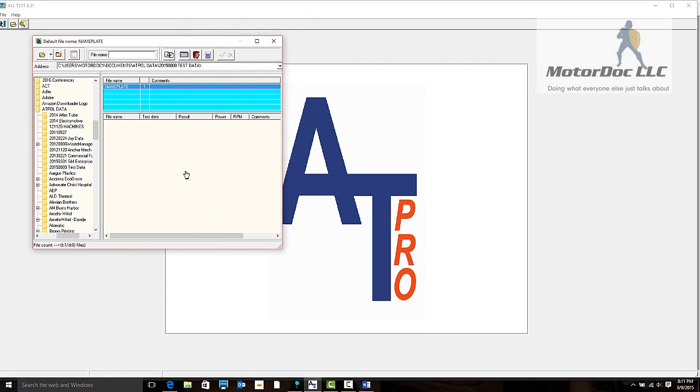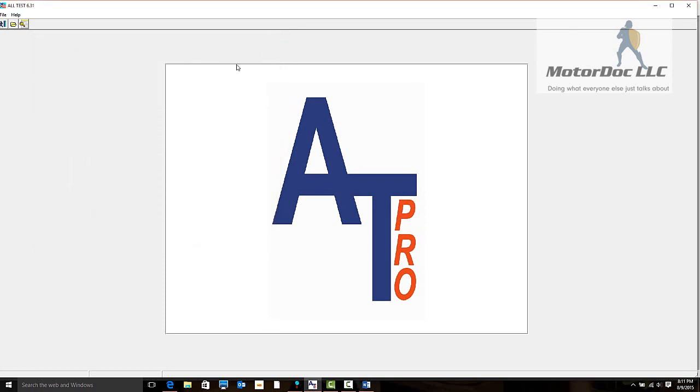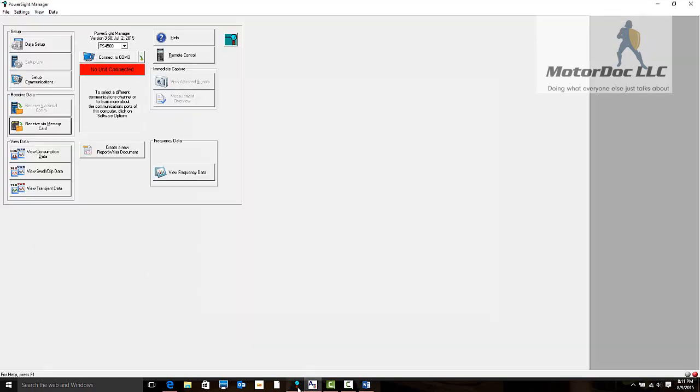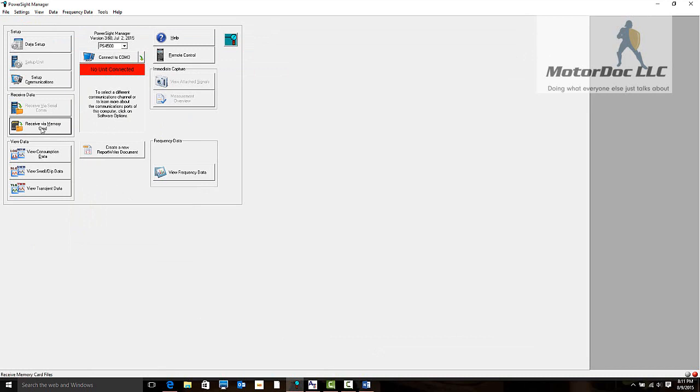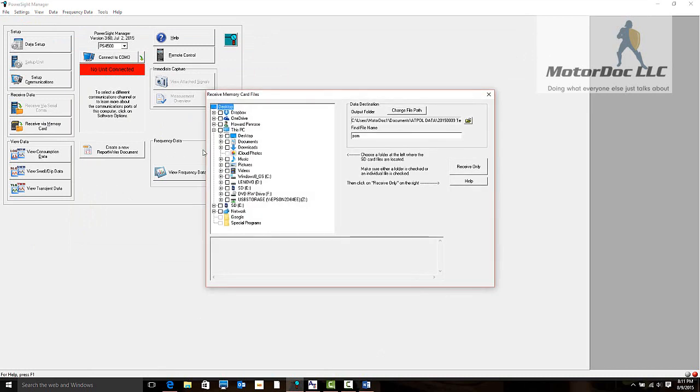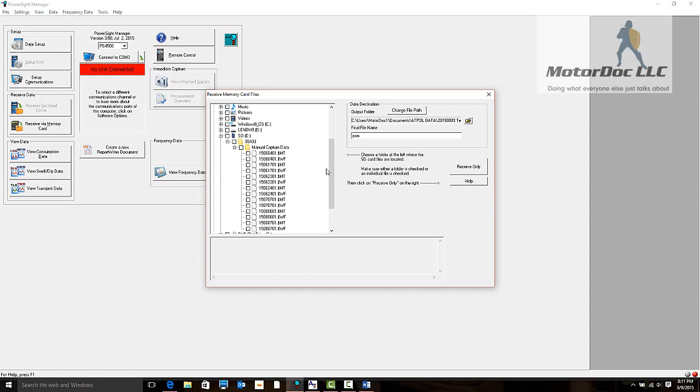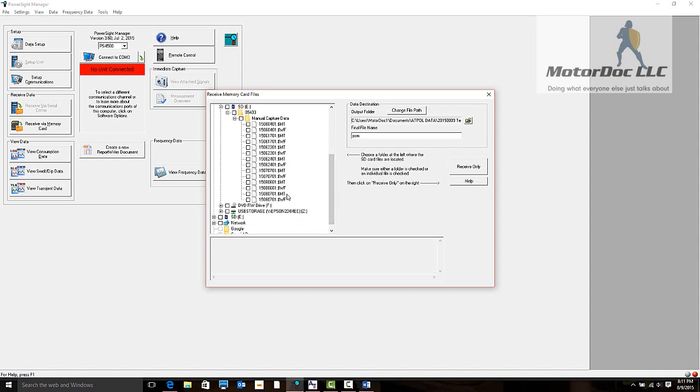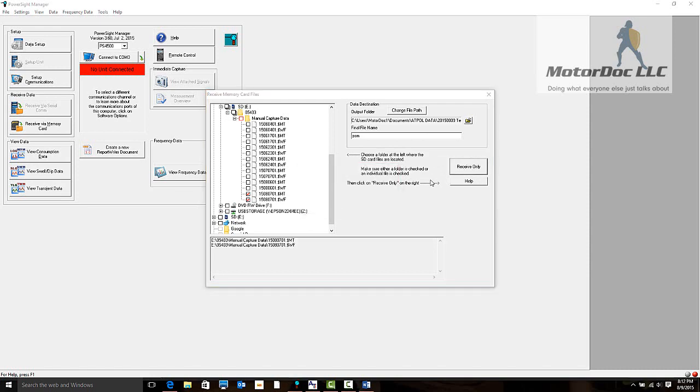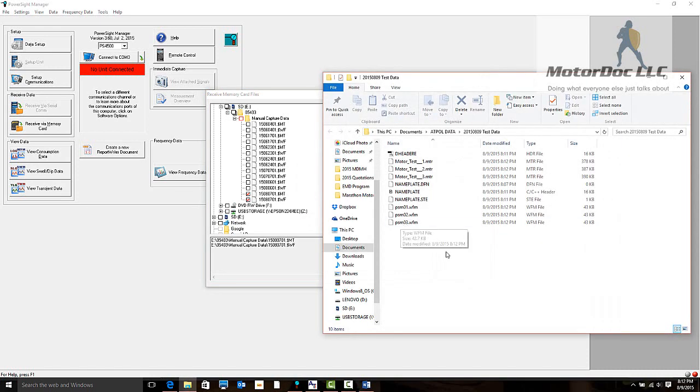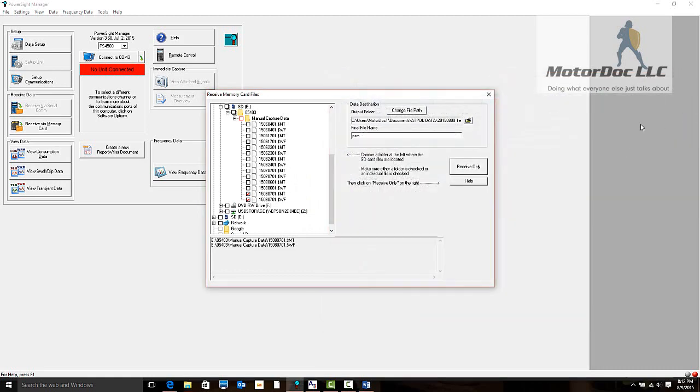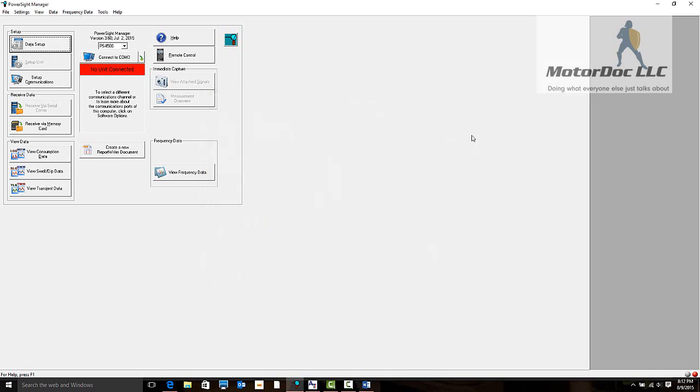We've collected the data. We've collected two sets of data on the machine. Let's close out of here for now and upload the data from a memory stick. We can do this either by connecting the instrument via Bluetooth or via a memory card. The SD card is here and we work our way down to the dates that were selected. You notice MT and WF. MT is the motor testing waveforms and WF is the power quality waveforms. I have my data set up to come into that folder that we have set up. Receive only. Our three sets of data have come in. There's our header, default header, all set up.